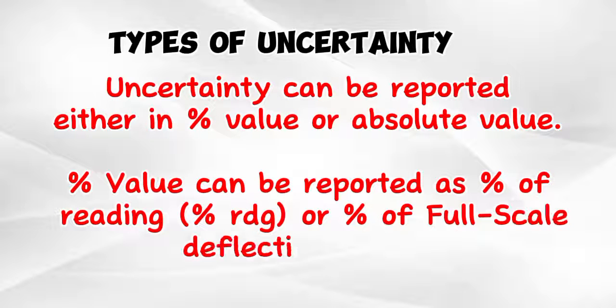During calibration, uncertainty can be reported either in percent value or absolute value. Percent value can be reported as percent of reading (% RDG) or percent of full-scale deflection (% FSD).